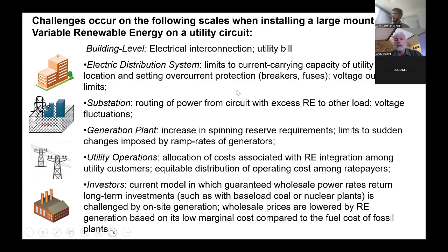With regards to the electrical distribution system, the local line would have to have the capacity to receive extra power from a distributed generation application. There's the protection scheme, which is the location and setting of breakers. One thing I'll digress on just a second: photovoltaic systems are not capable of delivering a short circuit current much higher than their normal operating current, so you have to think about how you detect a fault, because you won't have a huge current, much more than the typical operating current from a photovoltaic circuit. There's also voltage limits and reactive power.